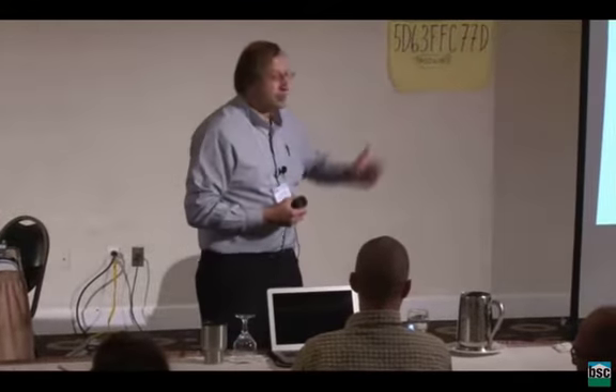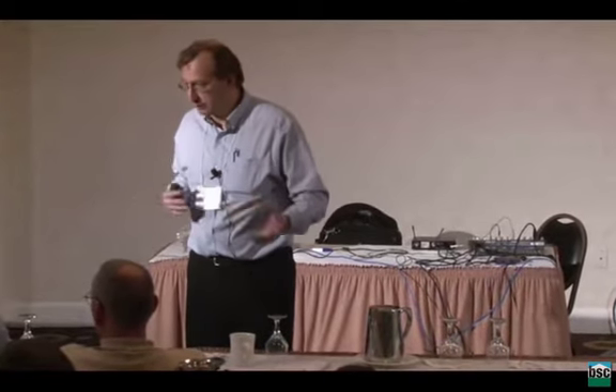Now, one of the potential solutions is that you don't have to have a wall wart. You could have what's called a slim duct unit, which is basically a fan coil that doesn't do much air pressure, so it has to be a short duct run. Usually it's like 8 feet long of duct, and it just blows right into a grill. So if you're making rich people's houses in China, you would use things like that. They would have grills high up, and they're quiet, and then the grill blows the cold or hot air in, and it sucks the air from a grill in another room, so you move air between two rooms, or you move from the hallway to the rooms, leaving all these units in the hallway so that you can access it without entering the bedroom, things like this.